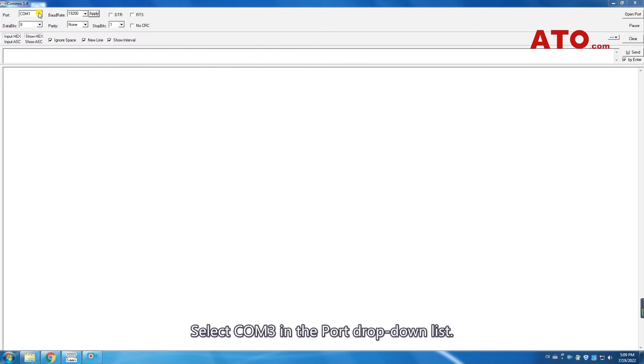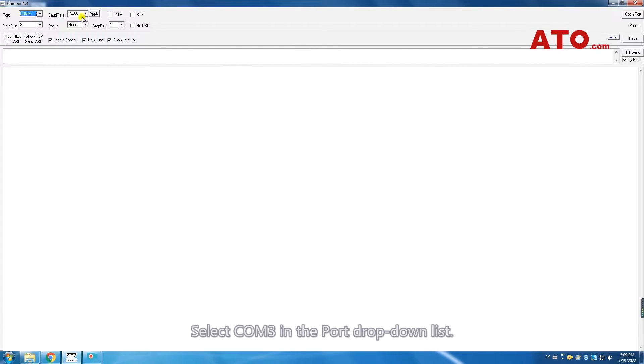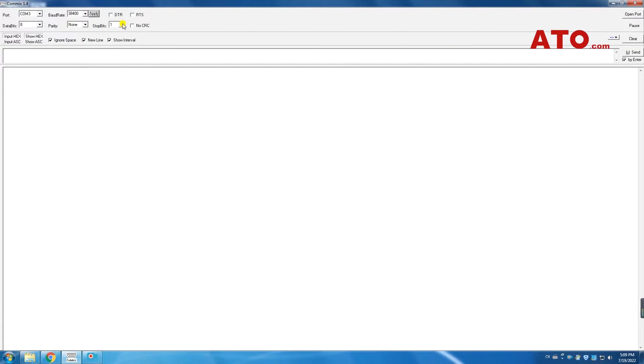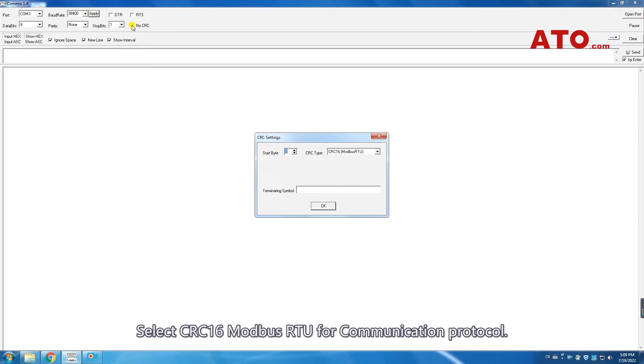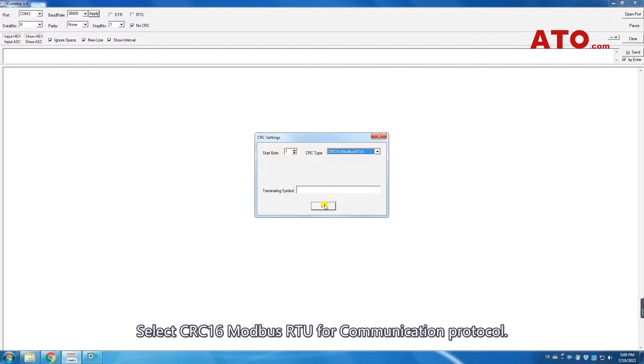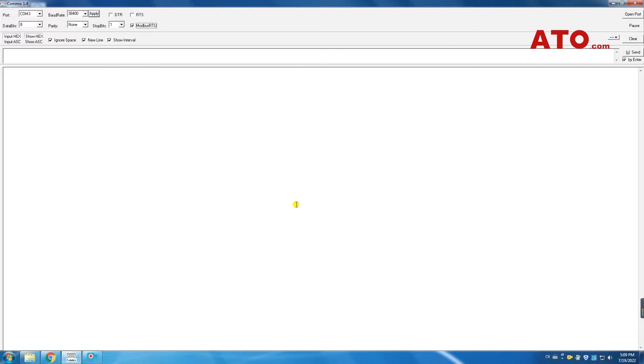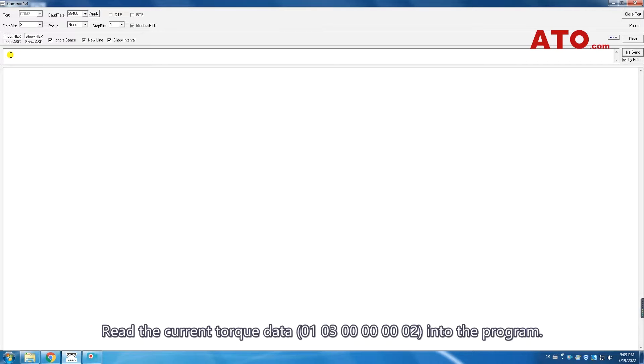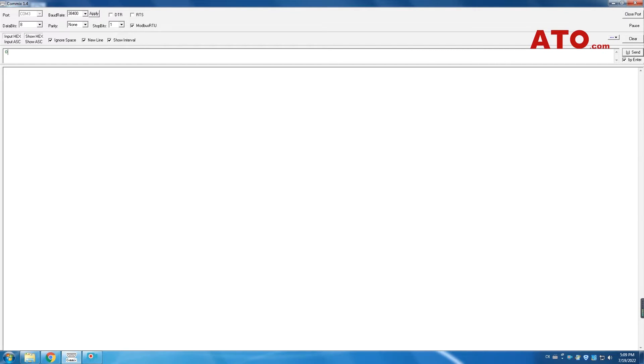Select COM3 in the port drop-down list. Select 38400 for baud rate as shown on the sensor screen before. Select CRC16 Modbus RTU for communication protocol. Read the serial port. Read the current torque data into the program.